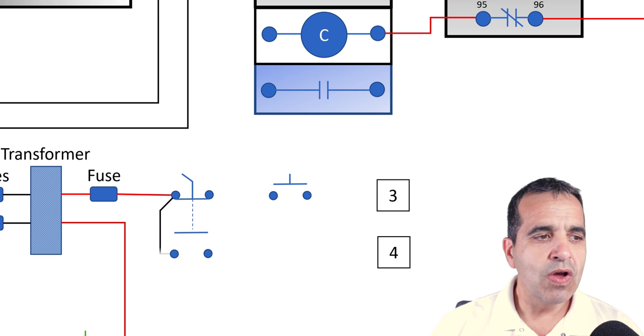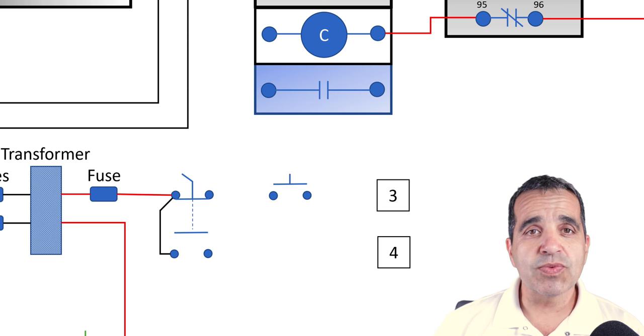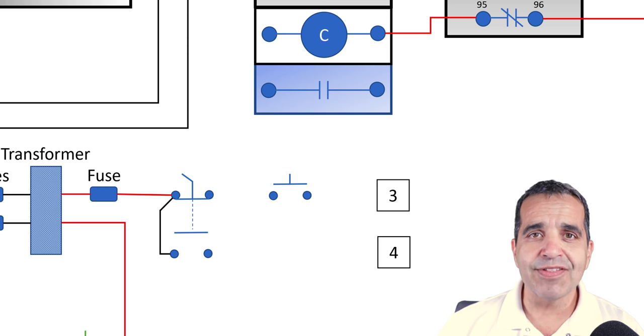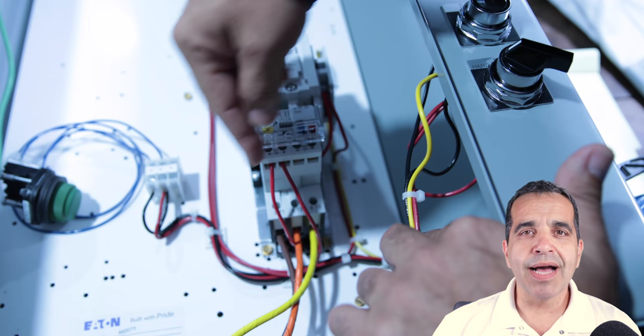From the fuse, we're feeding our selector switch. On the hot side of the selector switch, we're feeding both contacts through a little jumper. Then our selector switch feeds one side of our start button, and that start button is going to terminal block number three.